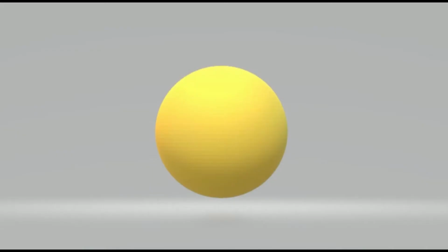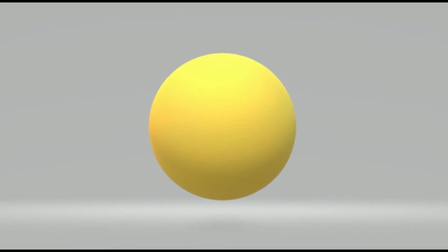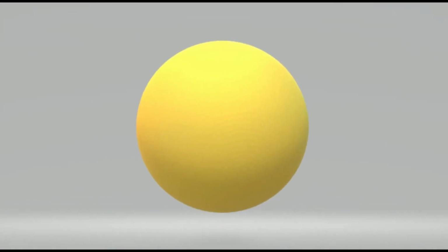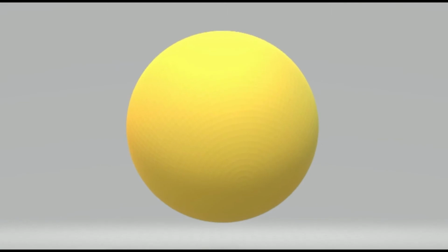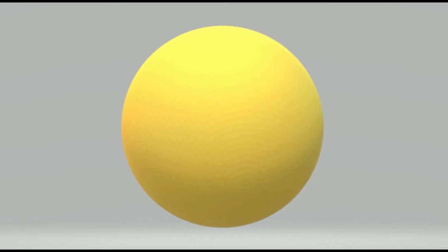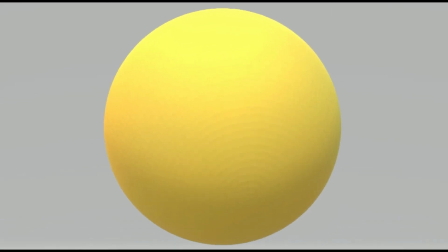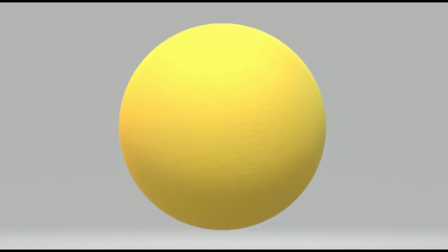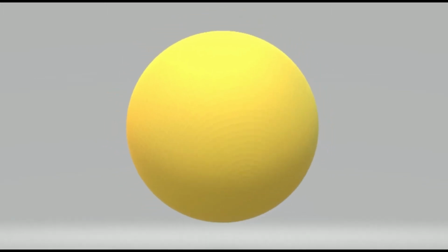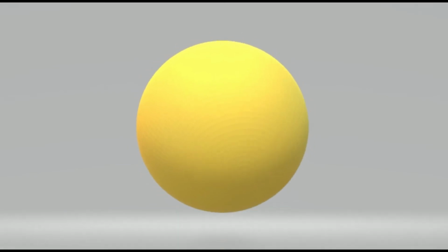Then the rinse step. As fresh water is introduced, the concentration of TDS on the outside of the resin becomes less and less. Once the TDS of the water outside of the resin is less than the salt concentration inside the resin, osmotic stress is created because of the high differential. This differential creates a condition that pulls water into the resin, causing the bead to swell. The styrene reacts, this time stretching and ballooning out to accommodate the flow of incoming water. As the rinse step continues, the water internal to the bead has a similar salt content as the water outside of the bead, and the elastic memory of the styrene cross-linkage pulls the resin back to its original size and shape.